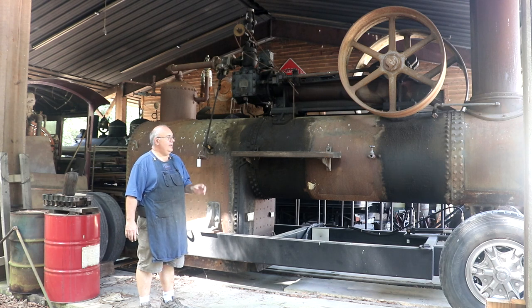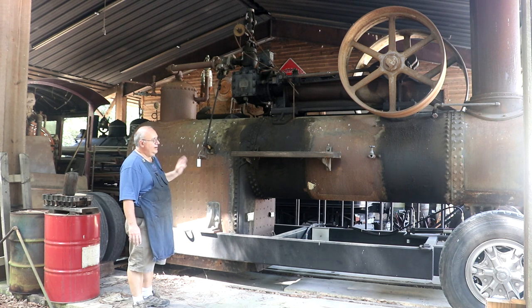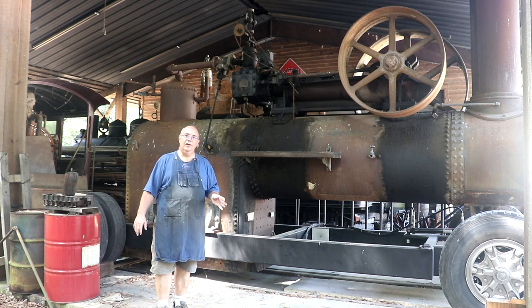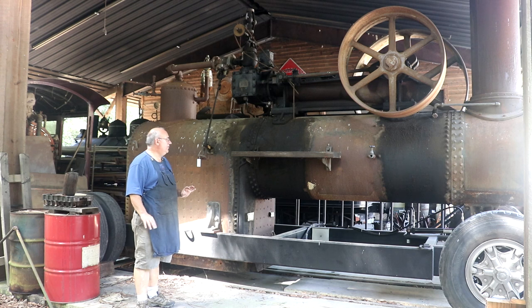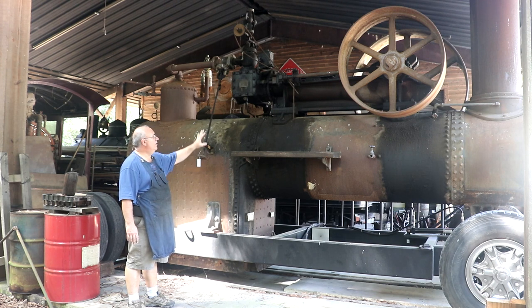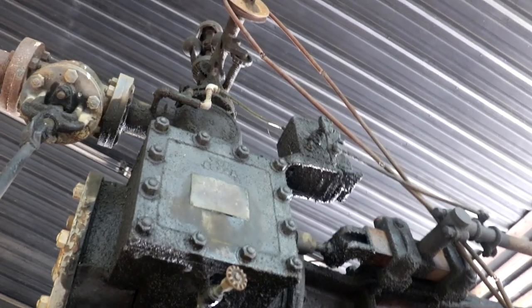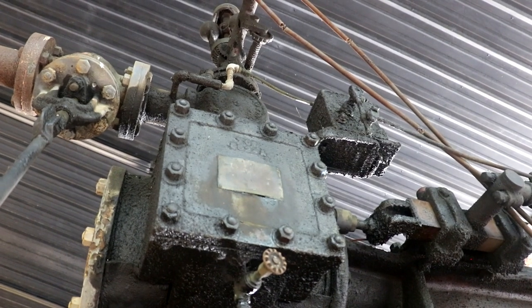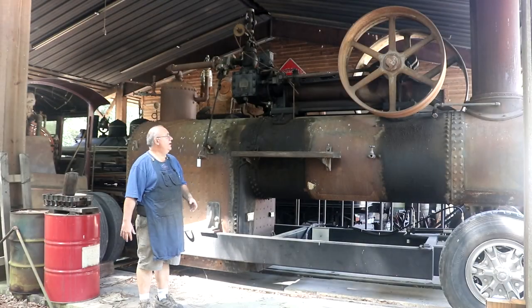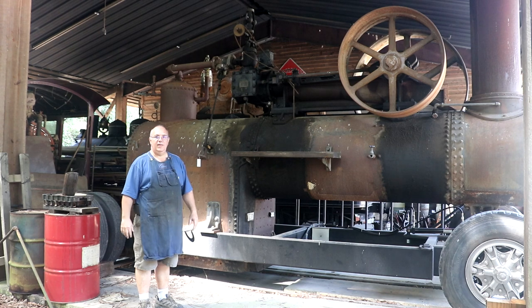Fortunately, we had a capital campaign several years ago and were able to raise the money to get a brand new boiler built — a modern welded, ASME-certified boiler that meets all modern codes, which the insurance companies are fine with. When we did that, it was decided we would use a different engine and actually downsized a little bit to about an 80 horsepower engine, also made by Frick. We worked with Jonah Stutzman, an Amish boilermaker and steam engine guy who built the new boiler and restored the steam engine. We purchased all that from him and currently run our exhibit each fall using that setup.